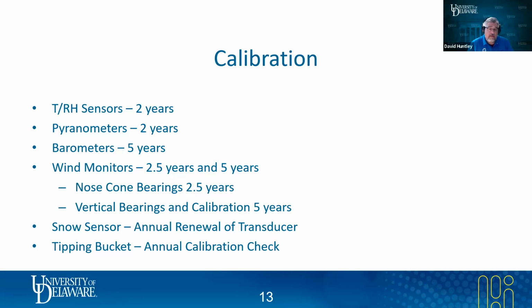Our wind monitors have a split calibration. The nose cone bearings get replaced every 2.5 years, and the vertical bearings every 5 years, along with the full calibration. That's really out of an abundance of caution. We noticed that between 2.5 and 3 years, the wind monitor nose cone bearings either get noisy or they stop working, they break.